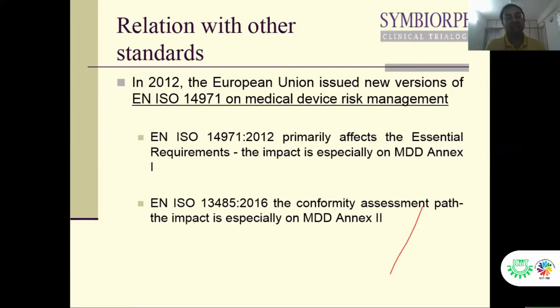ISO 14971 talks about the risk management system for medical device manufacturers. So you have to read the standard and apply the risk-based approach onto your system. This is the new requirement which came up in 2016. If you read the older ISO 13485:2012 standard, it has no mention of the risk-based approach.